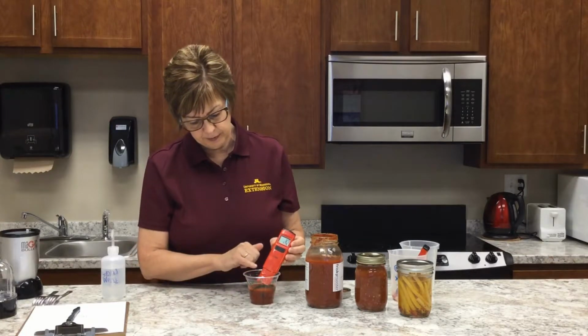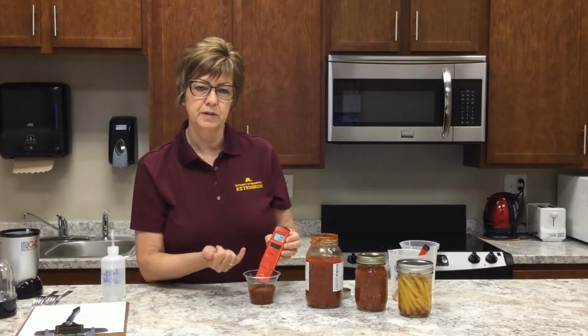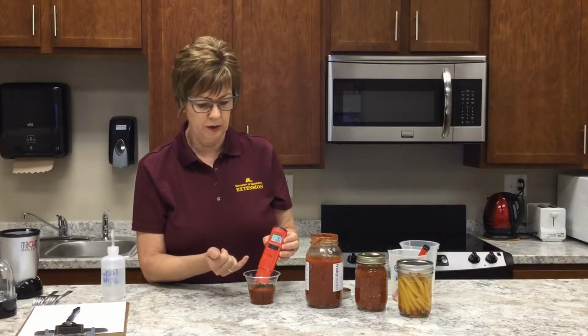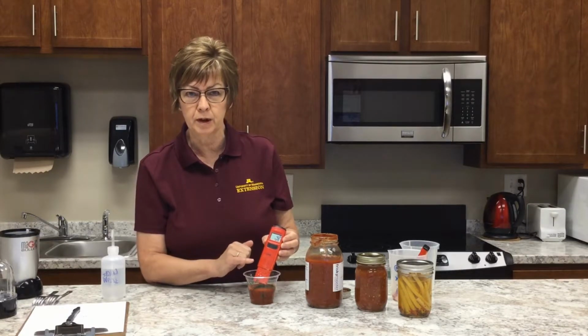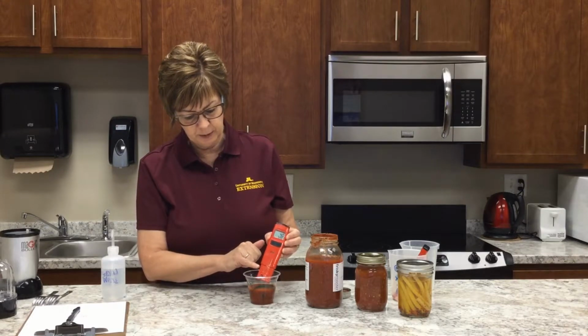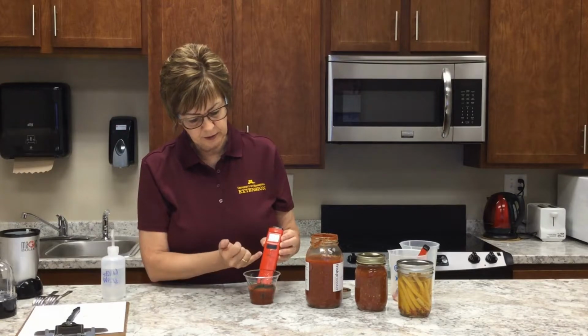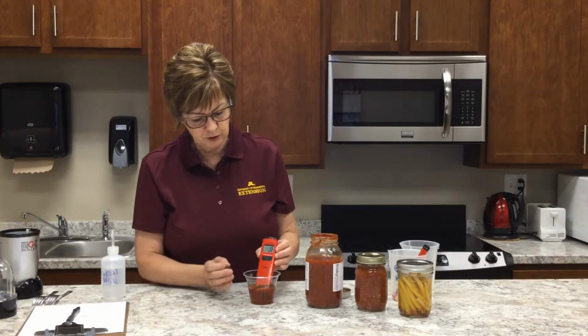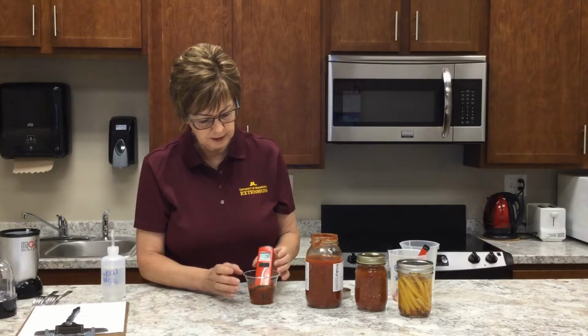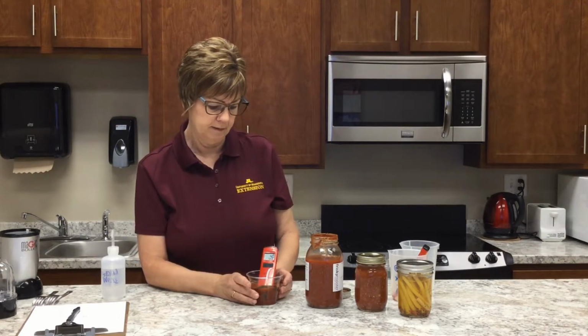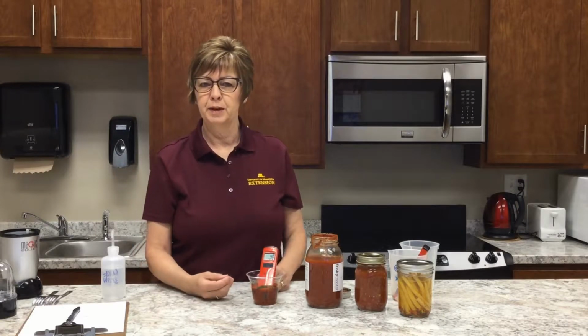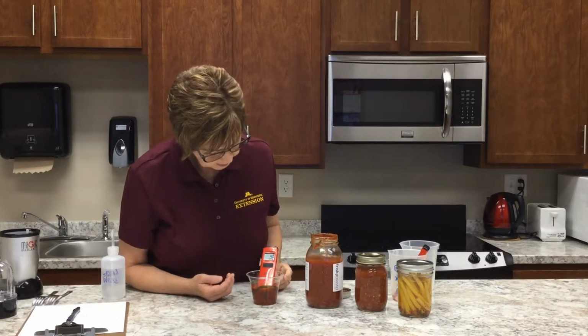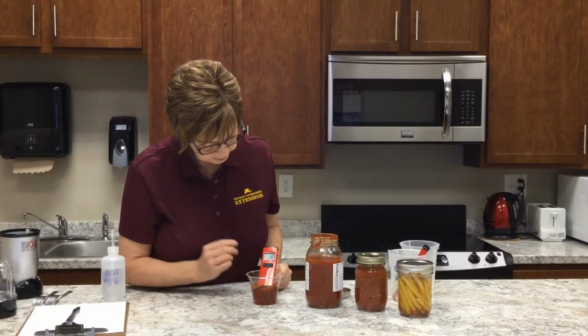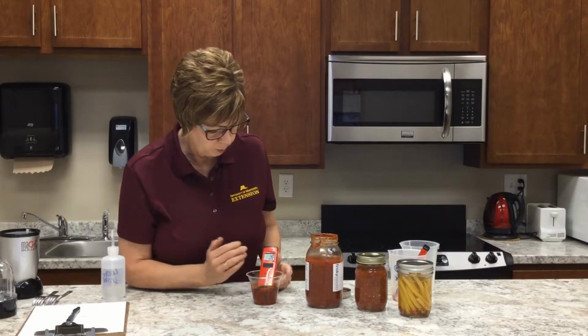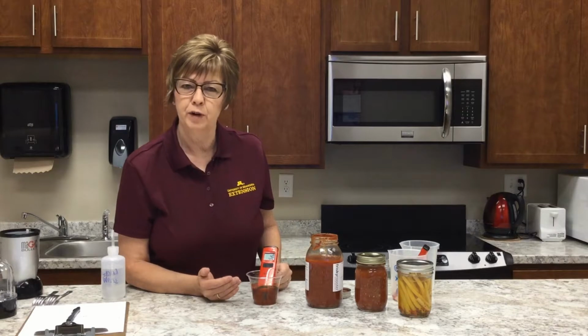Now, the meters that we have, and this would be specific to whatever meter you're using, you're going to want to make sure you look at the minimum level, and our minimum level is right here. There's a little indicator, and a maximum level is up here. So make sure you're testing enough product to get an accurate reading. So we'll let the pH meter do its thing. There's a little indicator that shows that it's testing, and once that's done, we have our result.